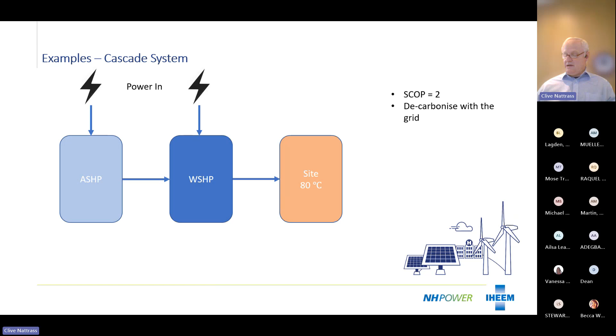If you use the model with this tempering solution, a staged approach, then as you convert plant from A and plant from B to low temperature, you can reconnect them to the low temperature hot water system - take them off at 80 degrees when you're ready, put them on the 40, 45 degree water system where, because you put nice new heat exchangers in, they no longer put load on the water source heat pump.